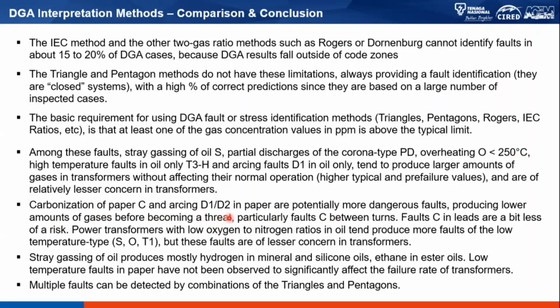So what it is saying is that sometimes in the transformer, D1 or D2 is already occurring, but the concentration of these gases is not well detected, although it is there. So what it is suggesting is that if in doubt, use the pentagon method, so that if such a situation exists, the pentagon method will be able to detect it. Okay. And then there are also issues on stray gassing of oil, which produces mostly hydrogen in mineral and silicone oils. These are some facts that have been gathered by the report of CIRED.